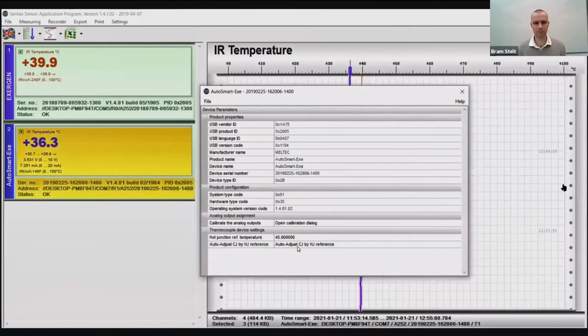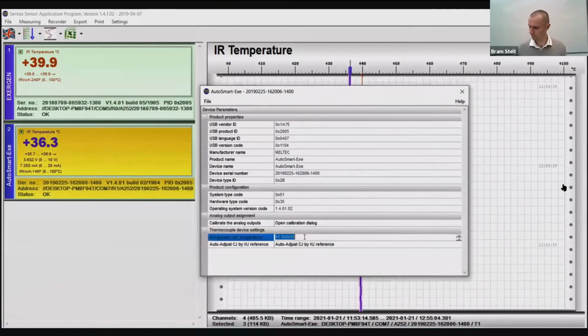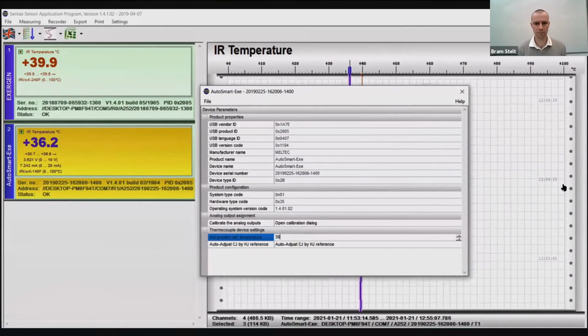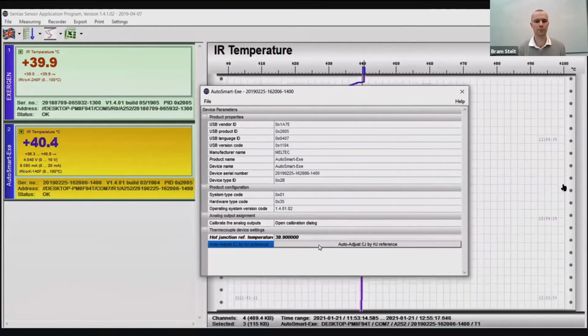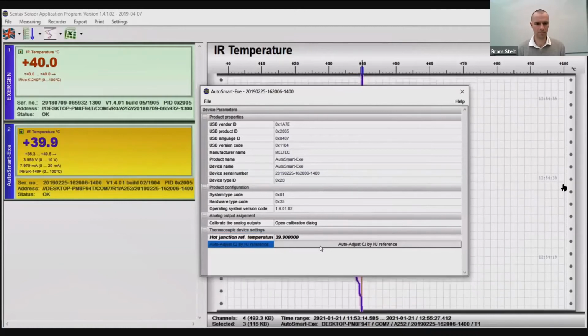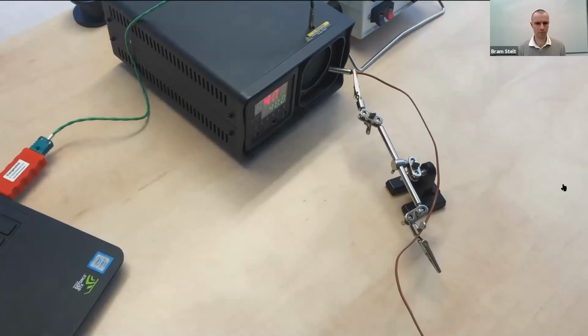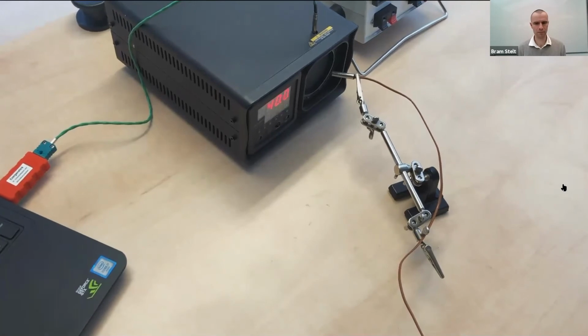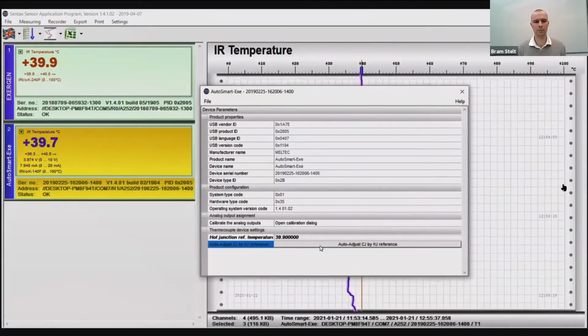So here on the software, I click. Now, my reference sensor is 39.9. I put in the 39.9 value here in the software, and then I press Auto Adjust. And then you will see the AutoSmart transmitter will automatically adjust the sensor reading to go to the set value of 39.9. And now, even though the sensor itself might be reading a slightly lower temperature because of field of view issues, it still gives a very accurate temperature reading as compared to the reference. And as long as in any application the environments are reproducible, the sensor will give you reproducible results. So now this sensor is custom calibrated.